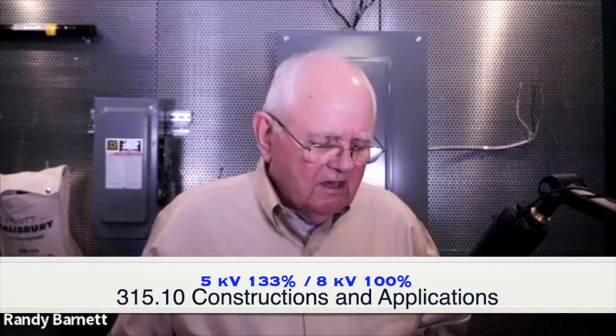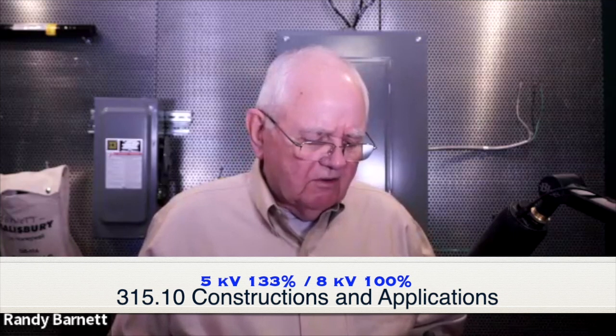So we see a lot of EPR used. Now, you'll also commonly see another type of insulation on this medium voltage cable, and it might be kind of pinkish or reddish in color. That usually is an indication that there's some type of lead oxide in that dielectric insulation. But nonetheless, this is all white. It is no lead EPR then. And let's see what else it tells us. It tells us that it is NL-EPR, then it says 5 kV, 133%, 8 kV, 100% insulation level.